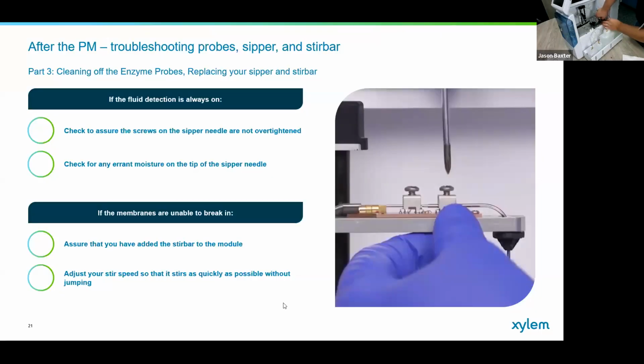You definitely want to make sure your waste tubing's connected. It'll make a pretty big mess otherwise. Here are some things that you want to do immediately after that. Make sure that the screws on the sipper needle are not over-tightened. It can sometimes cause an issue where it will crush down too much. You can see in the photo here, if you over-tighten that, it'll crush down into the board below, and you don't want that. It could tell you that you're always detecting fluid, and that's something we want to avoid.